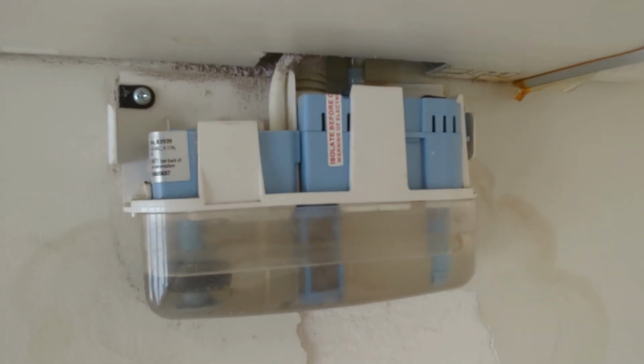Nasty. And now it seems like it's destroyed the condensate pump, because the complaint was that the unit would run for a few minutes and then turn off, and then later on it would run for a few minutes and turn off again. What we found was the little condensate pump, one of those Aspen mini white pumps, it's all got nail dust and stuff inside the motor. The pump itself is working, but it's working very slowly and runs for a long time. Usually when those little pumps work, they send all the water out and then stop. But this one was just going.